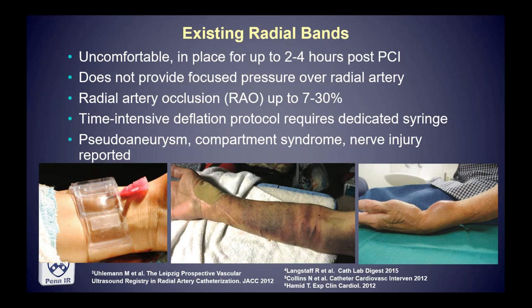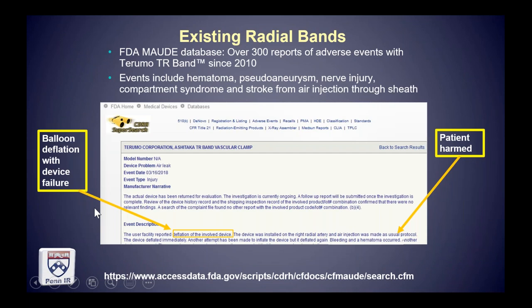When you go to deflate these balloons, if you deflate them quickly they can lead to re-bleeding. So there's a pretty time-and-labor-intensive deflation protocol. It requires a dedicated syringe — if you lose the syringe you have to open another device to get one. There are untoward effects like pseudoaneurysm, compartment syndrome, and nerve injury, not surprising given they're not selective and are compressing the entire wrist. The FDA MAUDE database has a plethora of reported adverse events including hematoma, pseudoaneurysm, nerve injury, compartment syndrome, and even stroke from inadvertent injection of air through the vascular sheath.